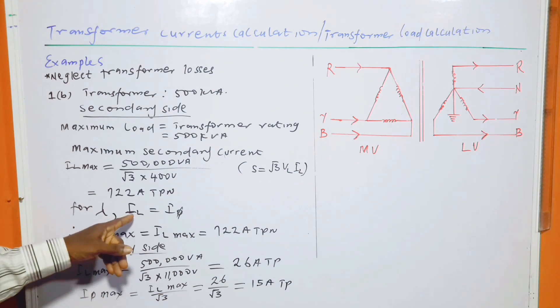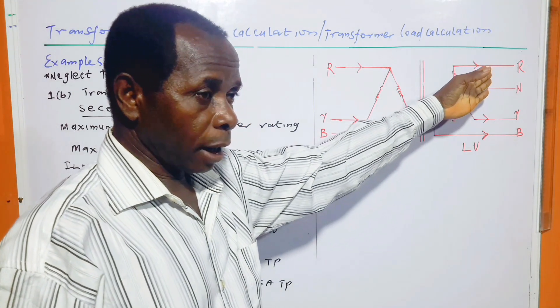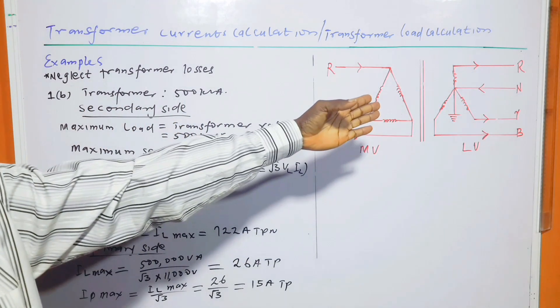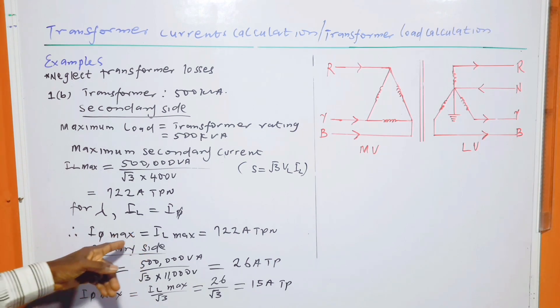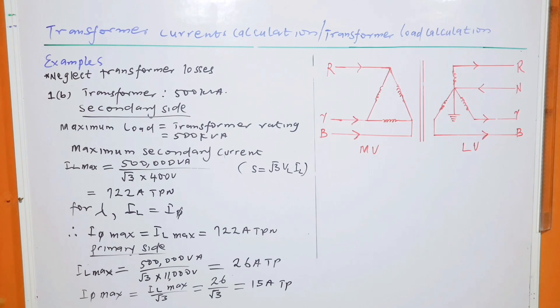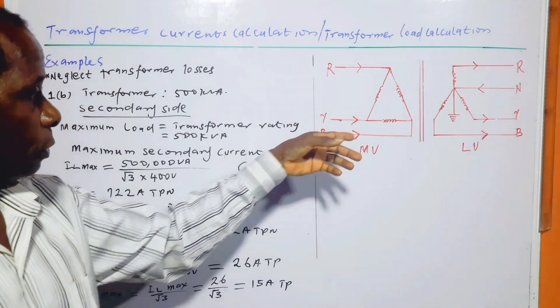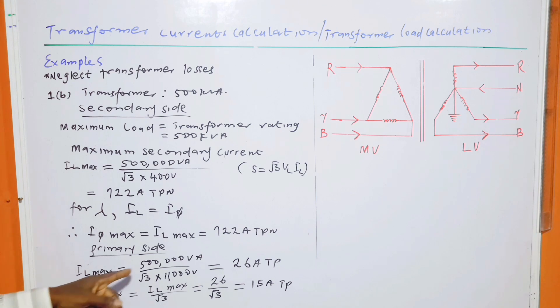For star connection I_line = I_phase, so the maximum phase current equals the maximum line current — both are 722 A. Moving to the primary side, the supply voltage is 11 kV, and substituting 11,000 into the formula gives a maximum primary line current of 26 amperes, three-phase.